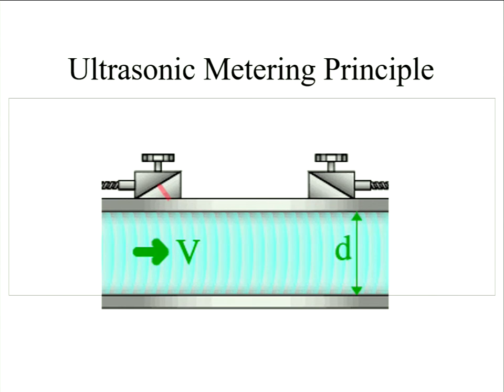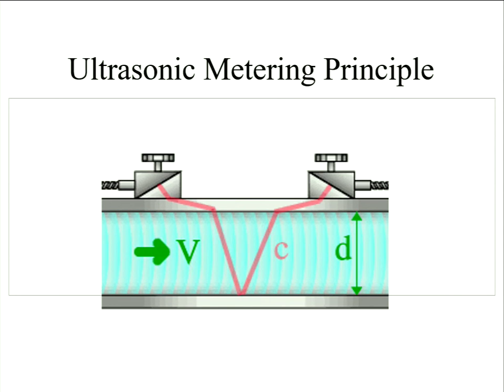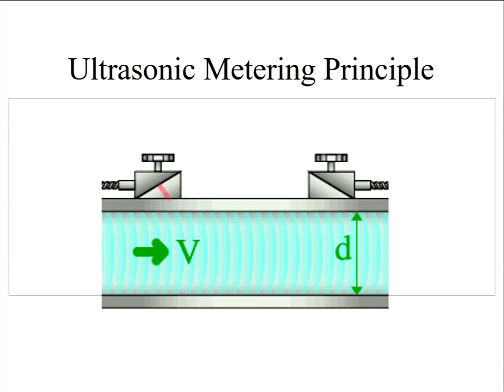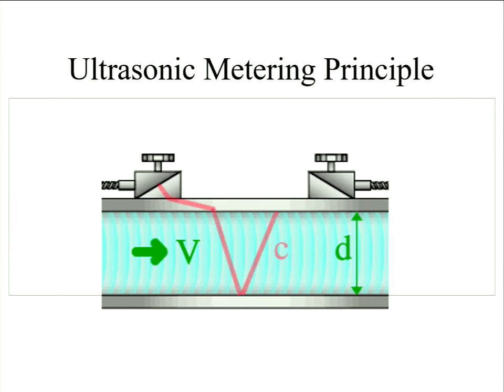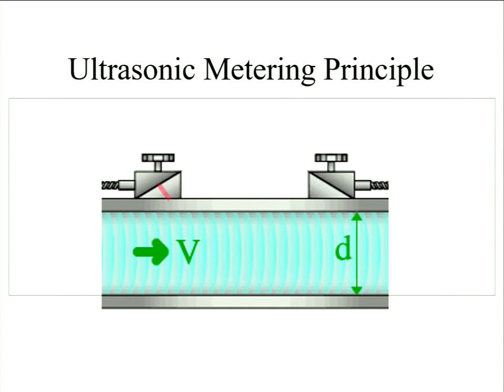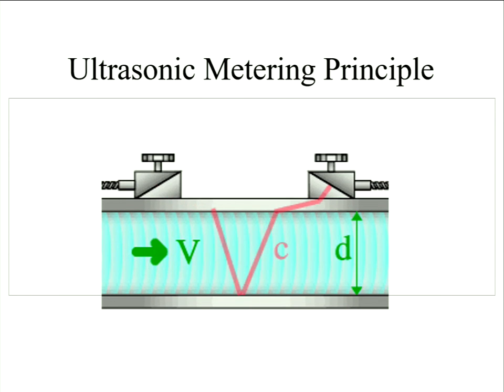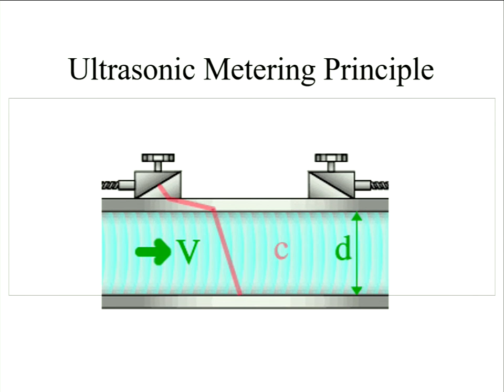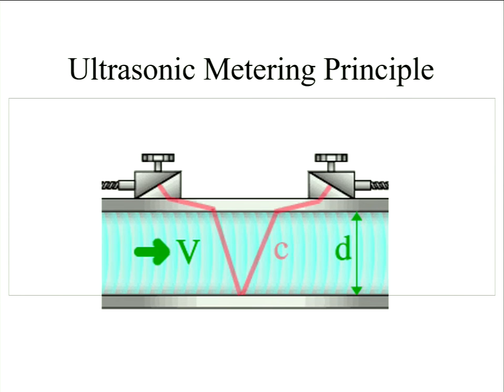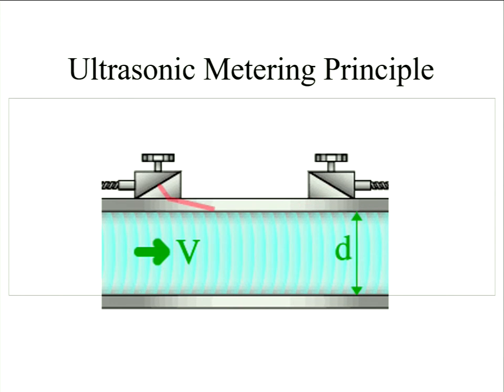So, for control, you just want it to respond and to be repeatable. If it's just, say, generally controlling the distribution of flow across the system, it might not matter to within a few percent. Whereas if it's fiscal, you're interested in long-term accuracy, so you need ultimately proper flow computers with composition information and all sorts of gas properties.